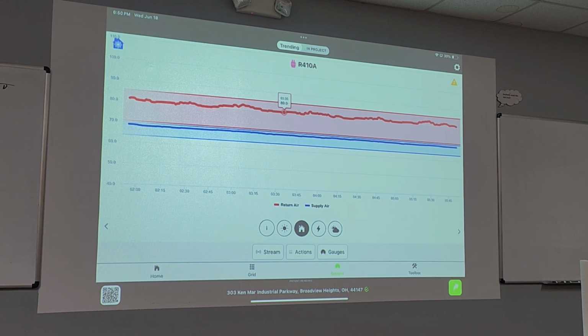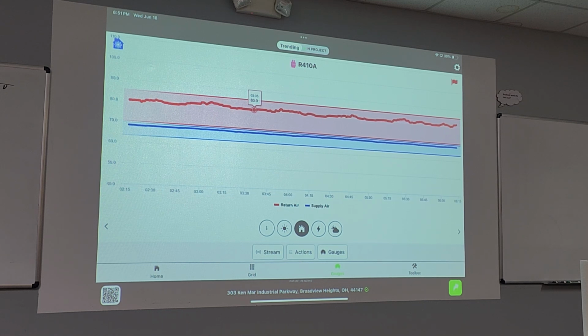So accuracy of measurements is everything here. Probe placement, by the way, ideal placement would be in the supply vent closest to the unit. This would be a bad room to do it in because you can't actually stuff the probe into the grill. You would want the probe stuffed inside the grill, not just in front of it, because you don't want any air currents to dilute the measurement the probe is seeing.